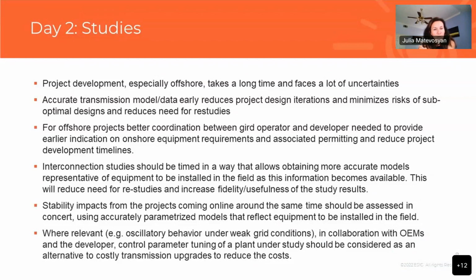For offshore projects, better coordination between grid operator and developer is needed to provide early indication on onshore equipment, because then they need to get associated permitting for that as well. And that may result in long development timelines. Interconnection studies should be timed in a way that allows obtaining more accurate models representative of equipment to be installed in the field, because information becomes available further on into project development.